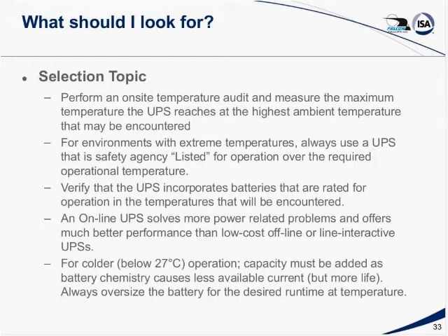Make sure that the batteries in it are rated for operation in these temperatures. And make sure, if you have any kind of critical monitoring, and I assume this is why anyone would employ a UPS to start with, that you use an online UPS rather than an offline or interactive type UPS. Do remember, though, that when you go into colder climates, you're going to have to add battery capacity, not life. Life is extended, but the chemistry in the batteries slows down, and you'll have to have more batteries for a given capability.